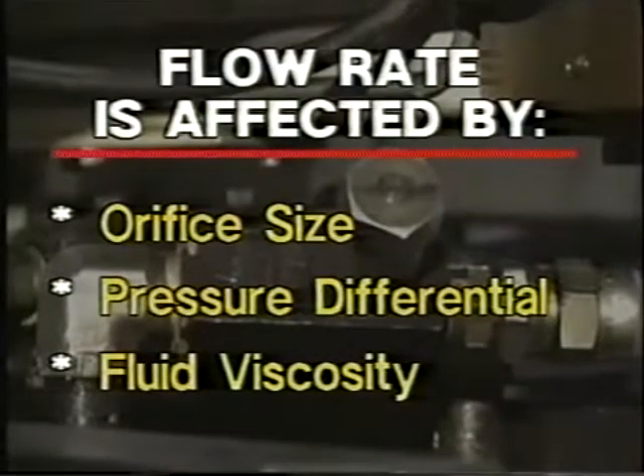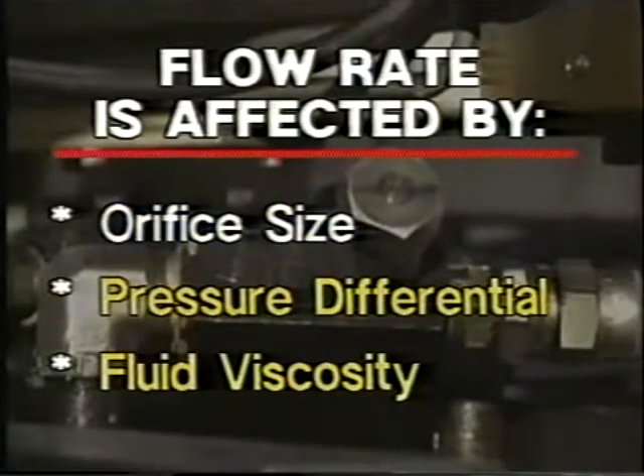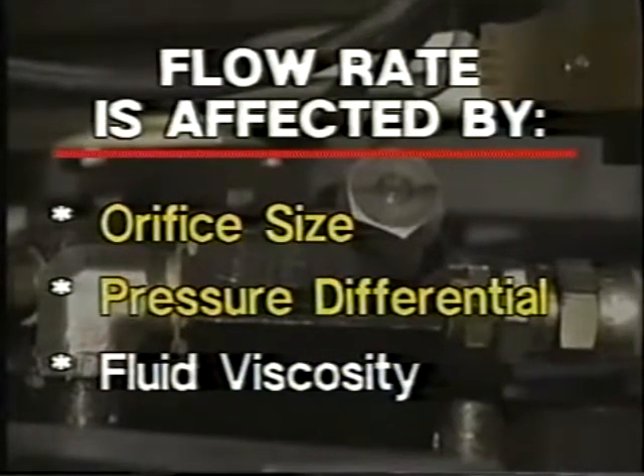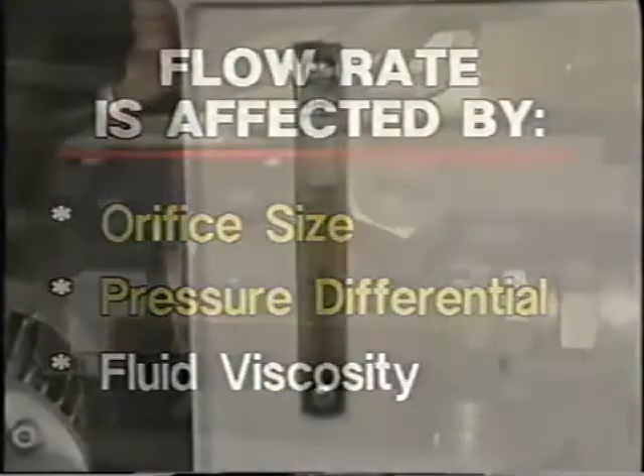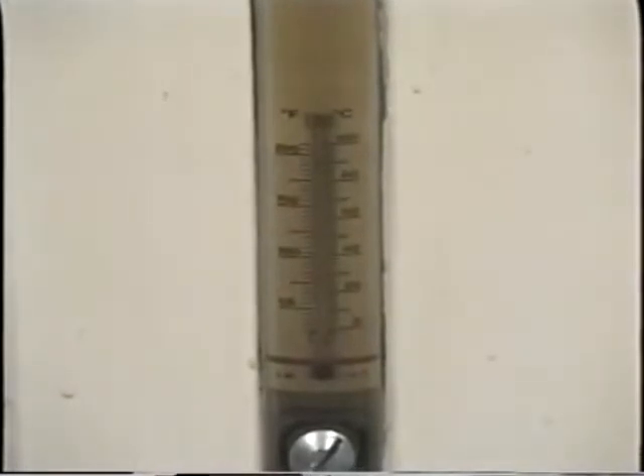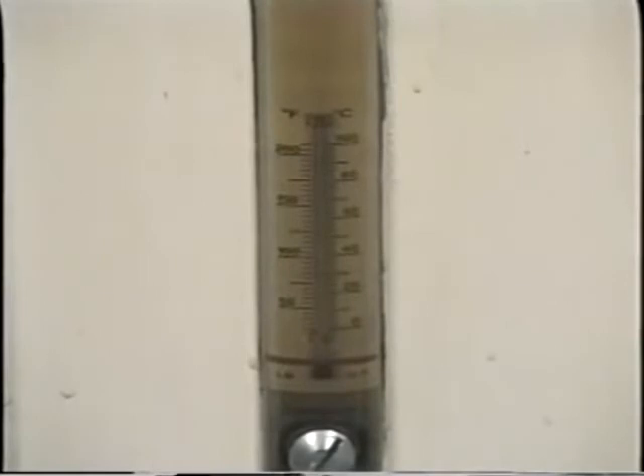So far, we've discussed two of the three main factors that affect flow: orifice size and the pressure differential across the orifice. The third is fluid viscosity. We learned in an earlier lesson that viscosity varies with changes in temperature. As fluid gets hotter, its viscosity decreases and more of it flows through the orifice. As fluid gets cooler, its viscosity increases and less of it flows through the orifice.